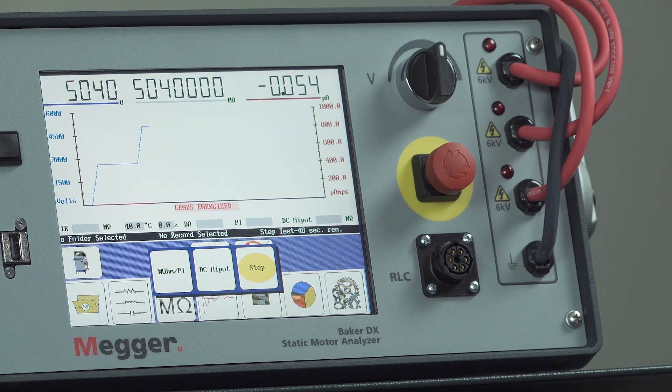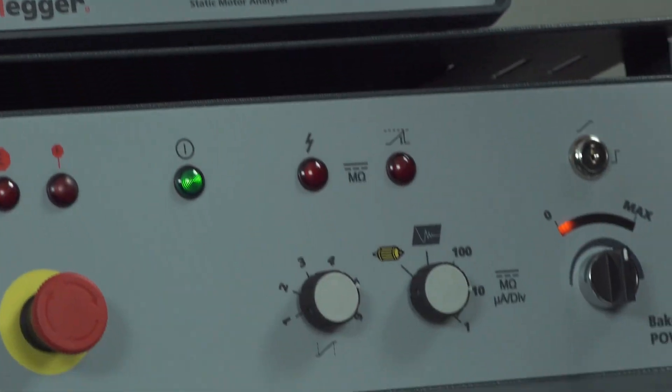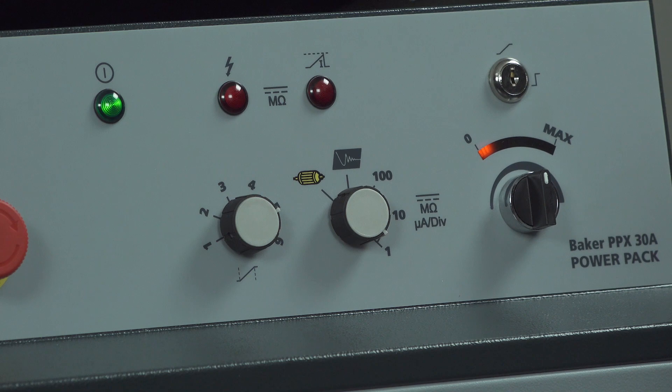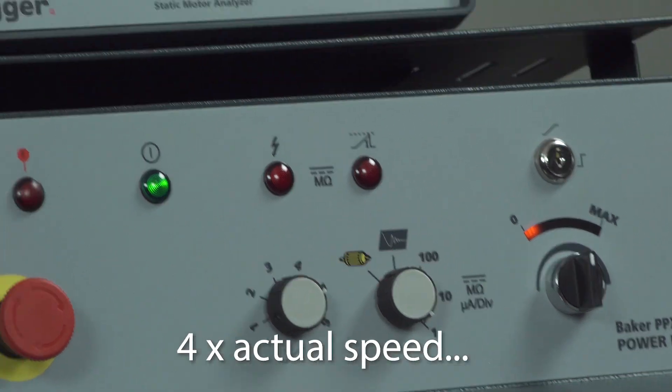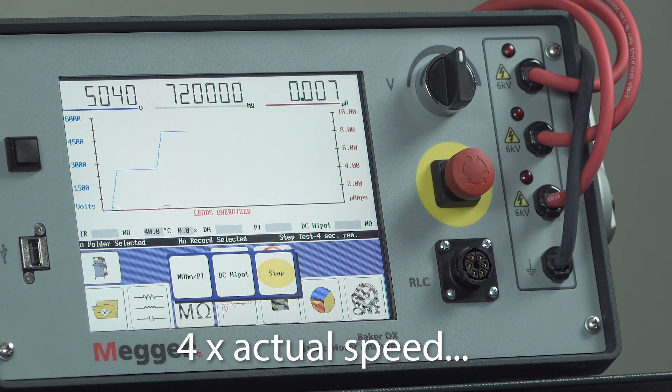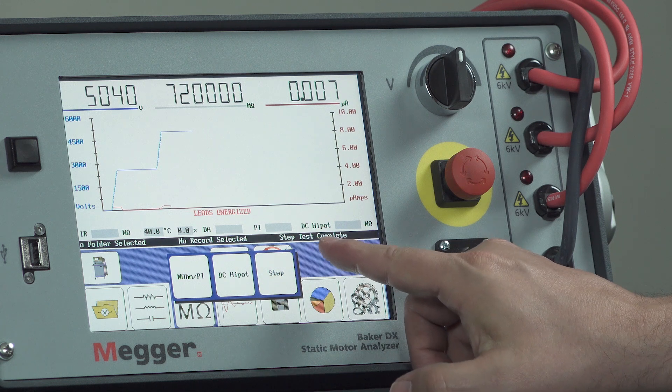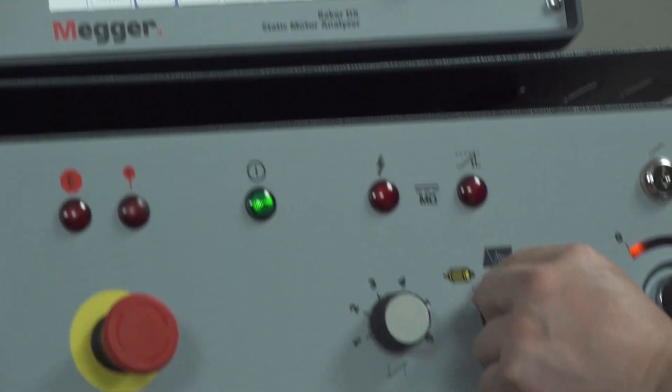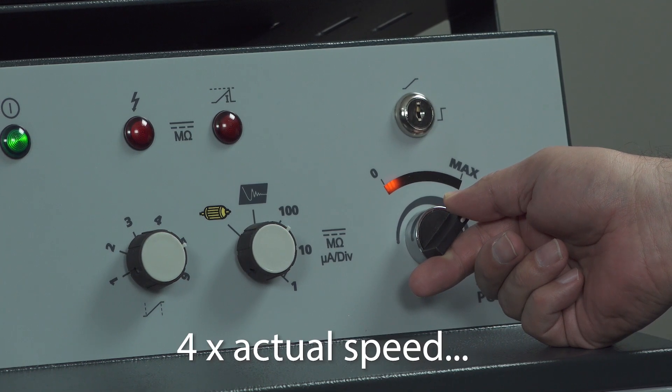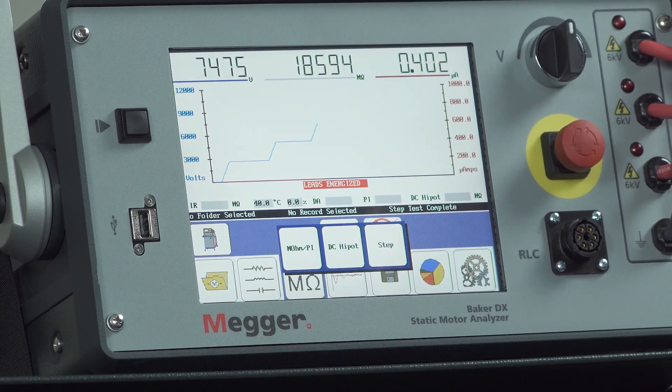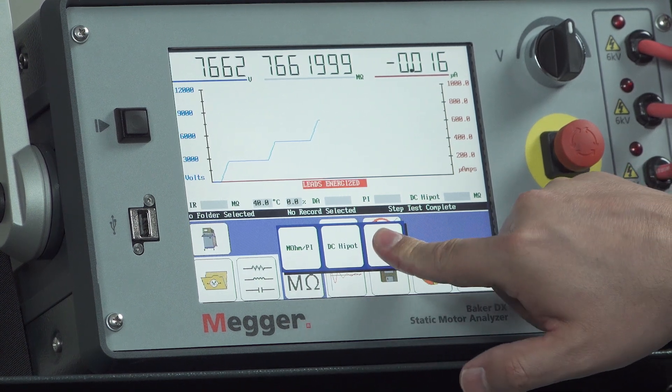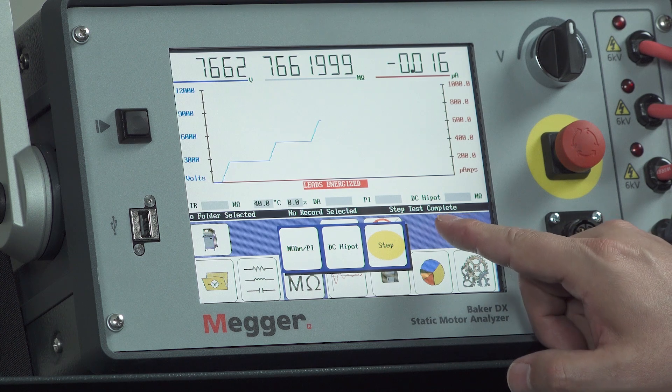Now to monitor the current, we're going to take that microamp per division setting and lower it to the lower range, as long as our current is low, to ensure that we're in the most accurate range for measuring the current. Our second step is complete. We'll take that function control switch back to 100 and then ramp the voltage to our next step, which will be 7,500. Now we've achieved 7,500 volts. Hit the step voltage or step button again. There we go, and we get a new step timer.